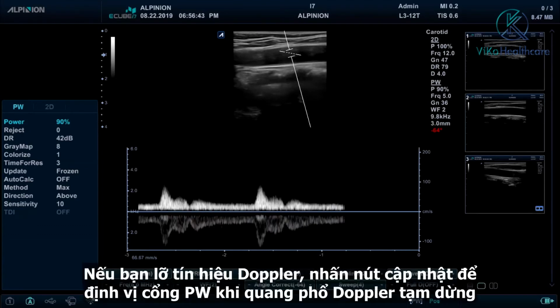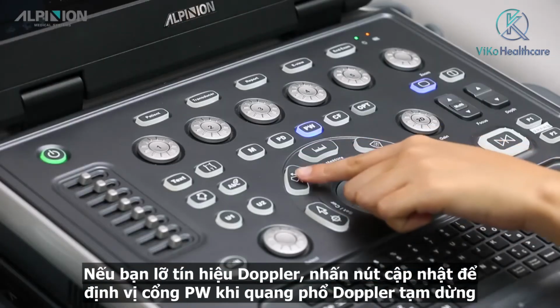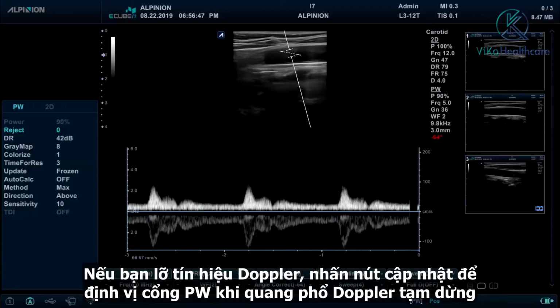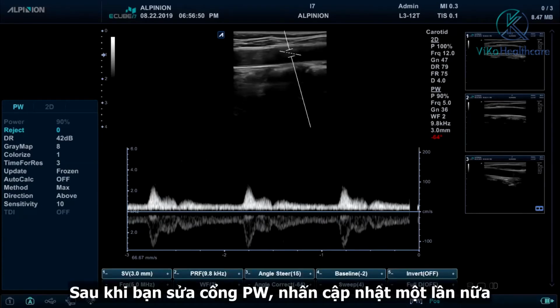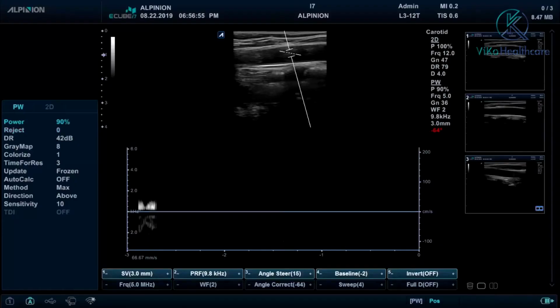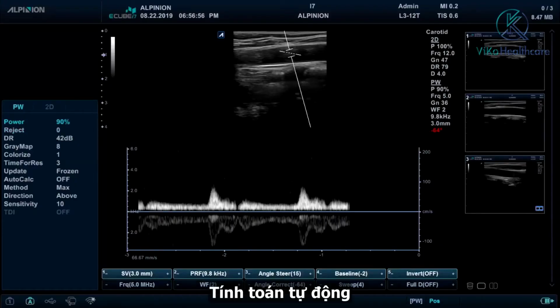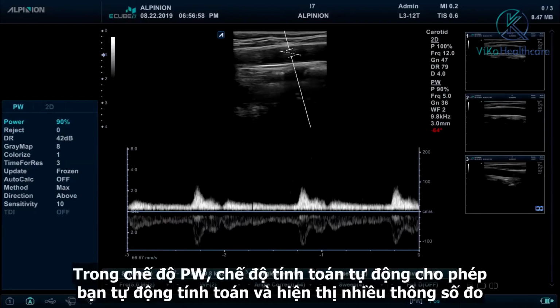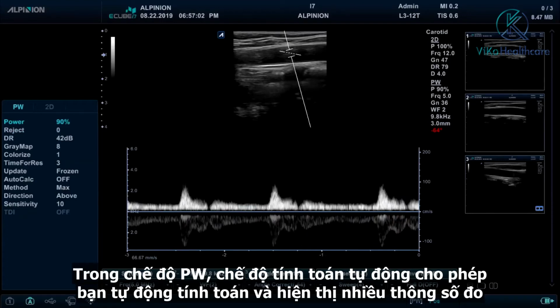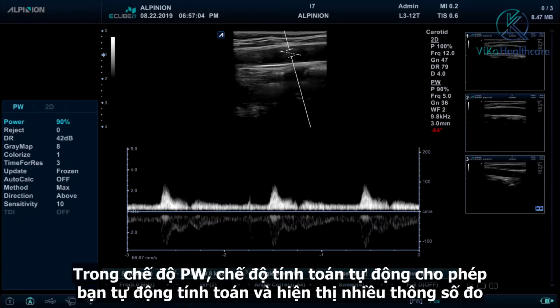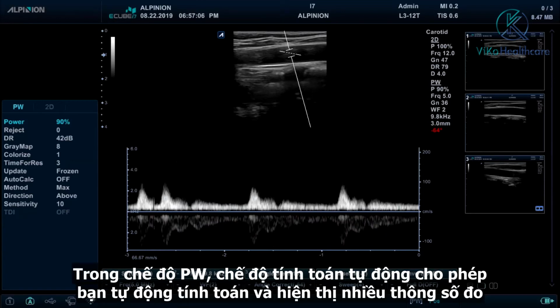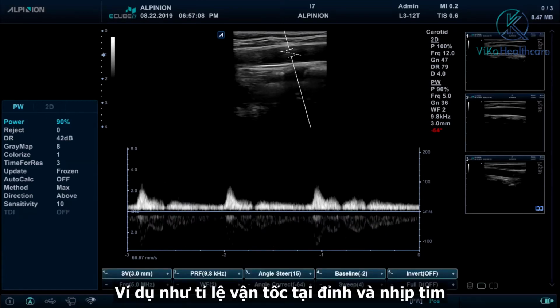If you miss the Doppler signal, press Update to relocate the PW gate while the Doppler spectrum is paused. Once you correct the PW gate, press Update again. Auto calculation. In PW mode, auto calculation mode allows you to automatically calculate and display a variety of measured values, such as peak velocities ratios and heart rates.